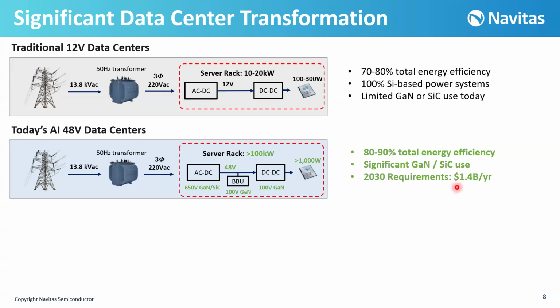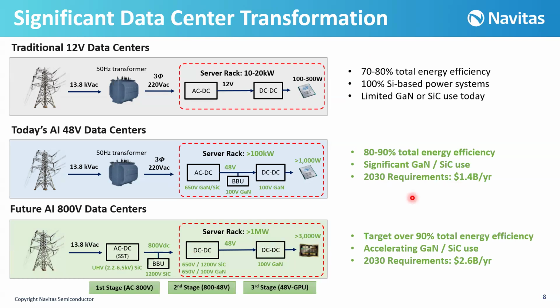Now let's talk about the future. In the future, we have the future AI 800-volt data centers. We are replacing the bulky 50 hertz transformer with a solid state transformer AC-DC converter, stepping down the high AC voltage to 800 volt DC, utilizing ultra-high voltage silicon carbide at 2.2 and 6.5 kilovolts. Then we use a battery backup unit utilizing 1200 volts. In the server rack, we step down again to 48 volts using a DC-DC converter instead of AC-DC, with 650 volt and 1200 volt silicon carbide, and 650 volt and 100 volt gallium nitride.